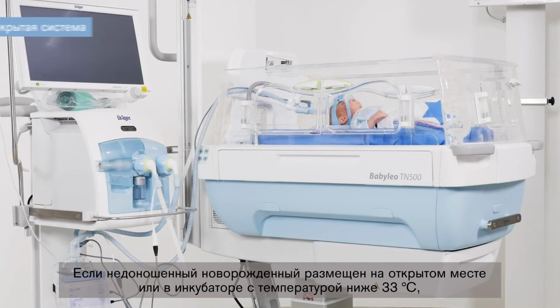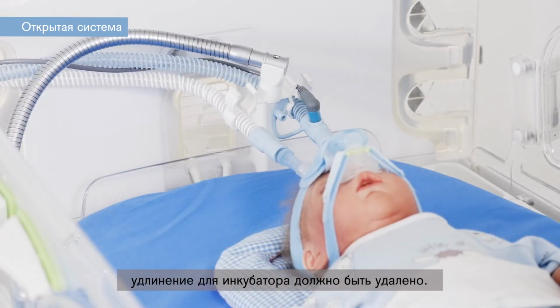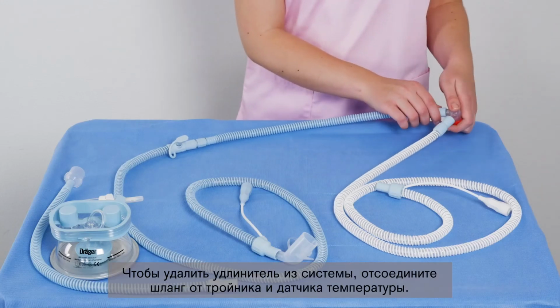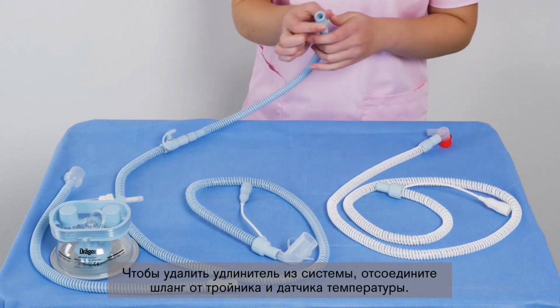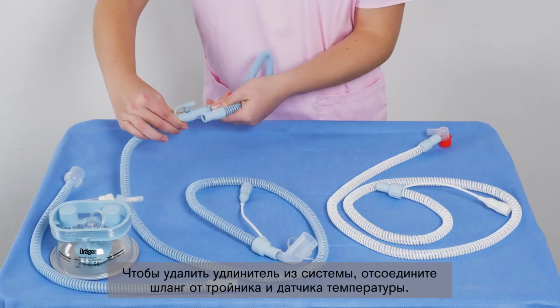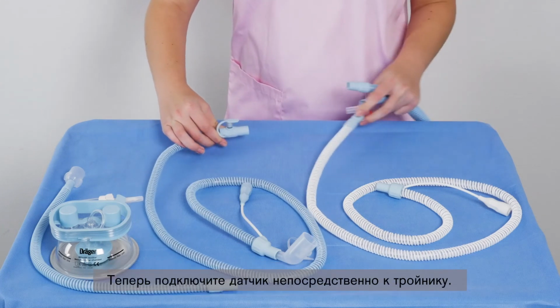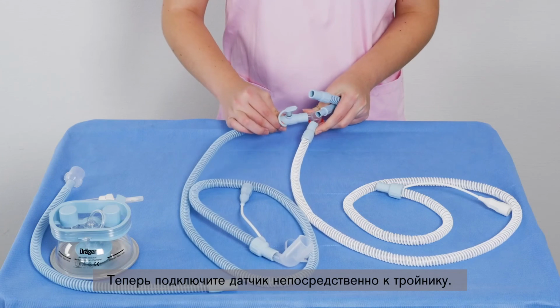If the premature infant is lying in an open care unit or in an incubator with a temperature lower than 33 degrees Celsius, the incubator extension should be removed. This reduces additional condensation. To remove the extension from the system, disconnect the hose from the Y-piece and the temperature sensor. Now connect the sensor directly to the Y-piece.